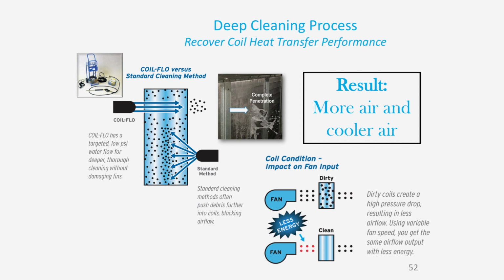Well, from the vendors that have approached us in the last few months to a year, we are finding that if you can get our coils clean, we can move more air through them. If you can move more air through the coils, one, it enhances cooling. Two, it keeps the air change rates proper, and it does give us a better chance to provide patients with a better environment in which to convalesce.